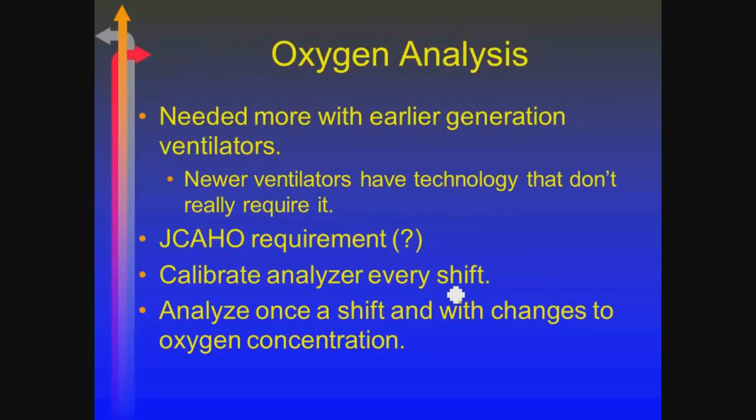Oxygen analyzers should be analyzed whenever you have a change in FiO2 or at least once a shift, and they should be calibrated also. Many of them have built-in oxygen analyzers already built into the ventilator, so it's kind of academic.